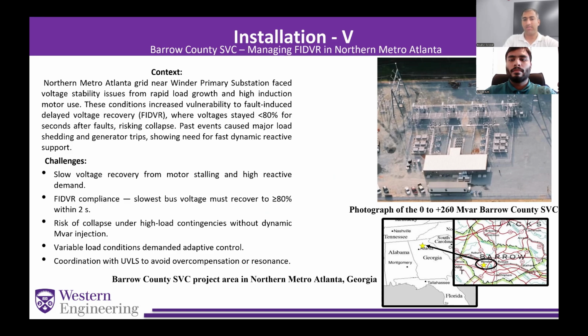And now I'll take over from installation 5, that is the Barrow County SVC. It's a North Metro Atlanta Winder primary 230 kilovolt substation serving fast-growing, motor-heavy loads that were failing FIDVR criteria, with voltages languishing below 80% for seconds after faults. Previous events had already forced UVLS and tripped generators. These are signals that the area needed dynamic var injection, not just static caps.